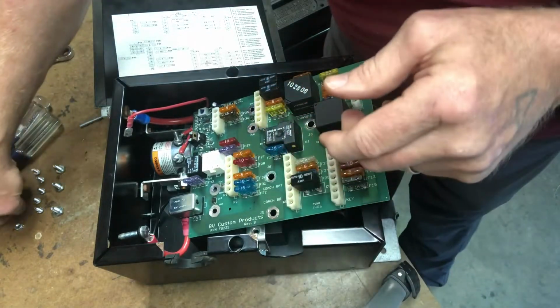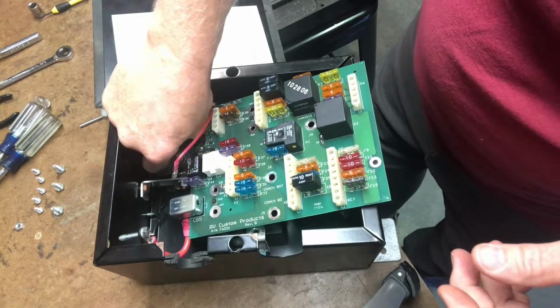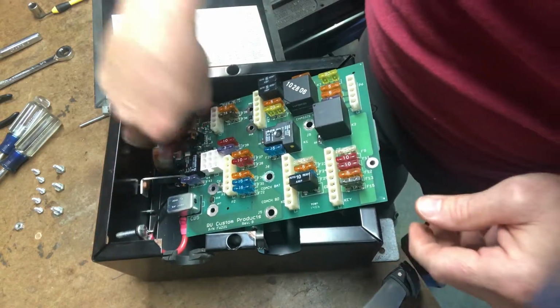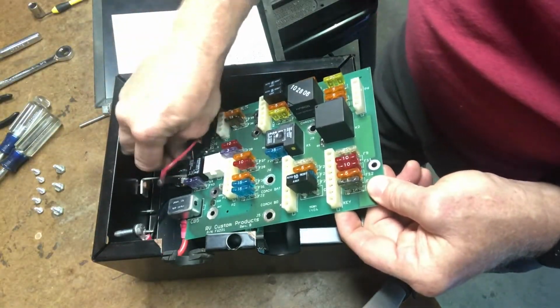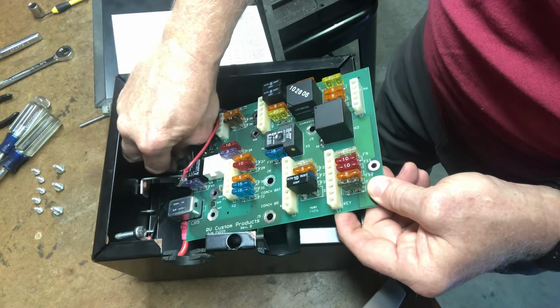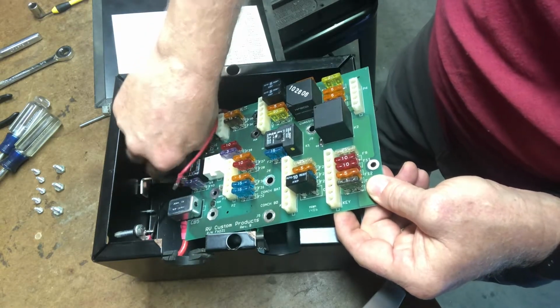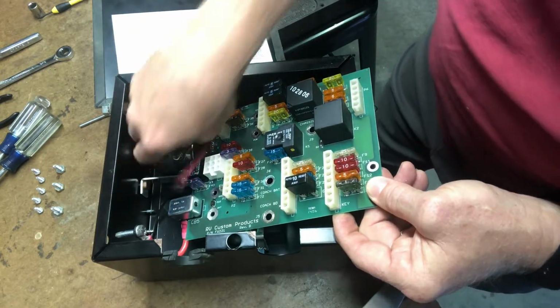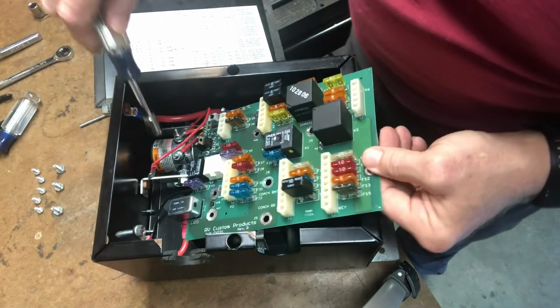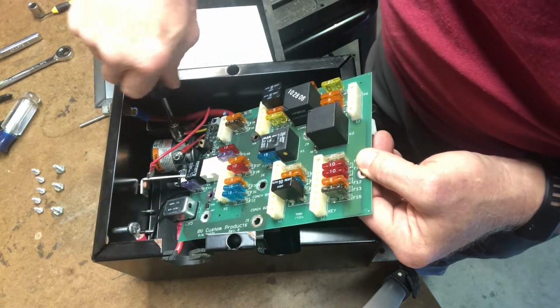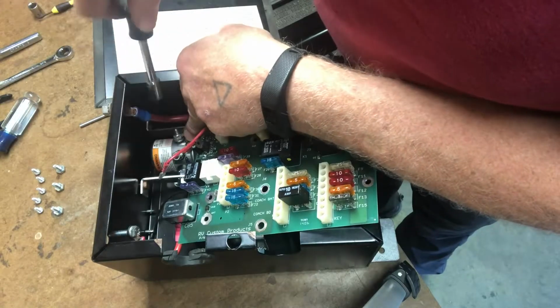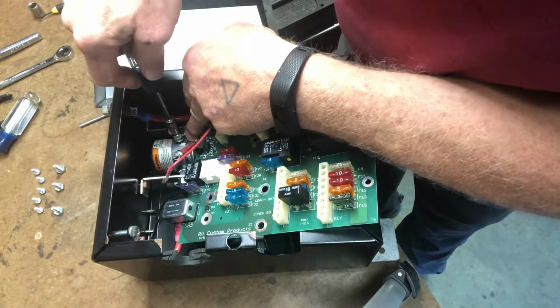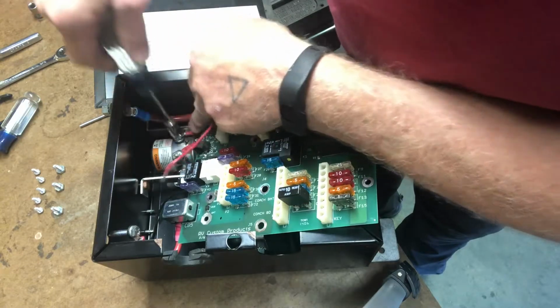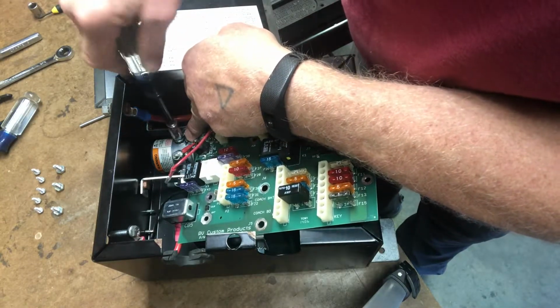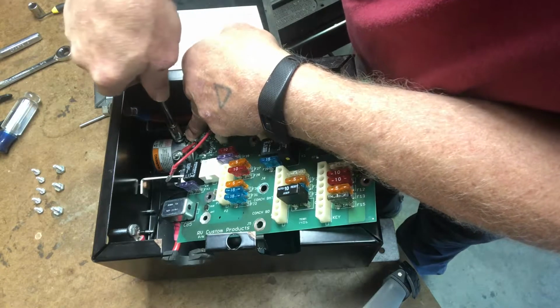Be really careful when you put these nuts on. They have integrated locking washers, star washers, to provide a positive electrical connection, and also to keep the nuts from backing off from vibration. Make sure you don't over-torque these, because you can damage the electronics or connections inside the solenoid. Ideally you'd put a backup wrench on the nut below, but if you're careful enough, you can. I usually hold the terminal lug back and tighten this just until I feel the star washer has compressed completely.